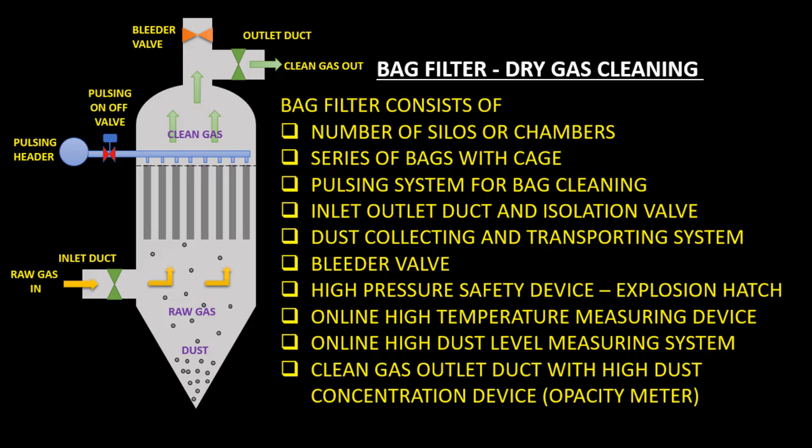It also includes a dust collecting and transporting system, a bleeder valve to release excess pressure, a high pressure safety device, and an explosion hatch to avoid excessive damage. There is an online high temperature measuring device to avoid damage such as burning of bags, an online high dust level measuring system, and a clean gas outlet duct with an opacity meter to identify bag leakage and monitor dust emission per environmental norms.